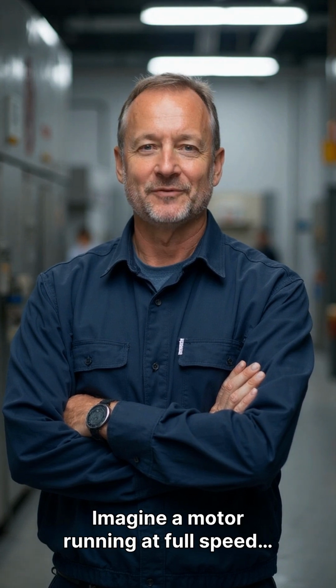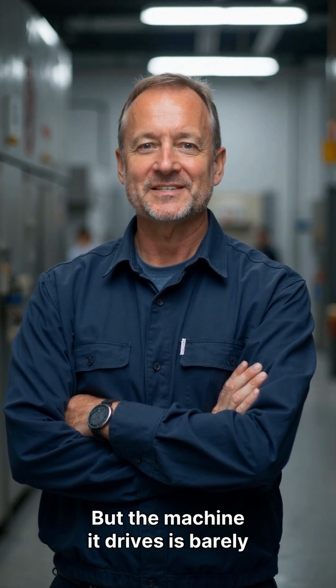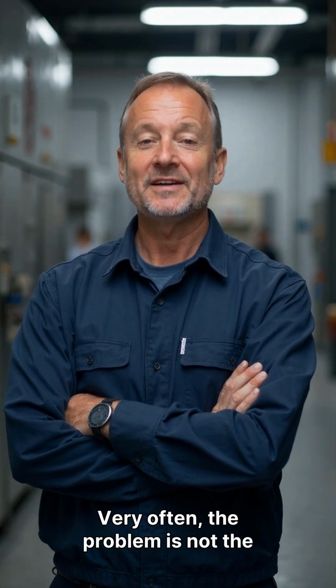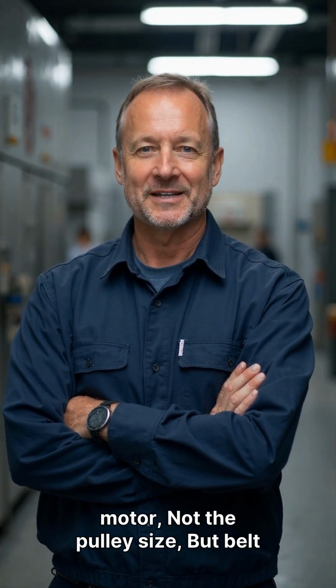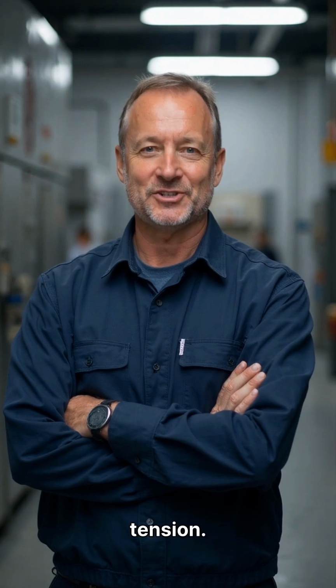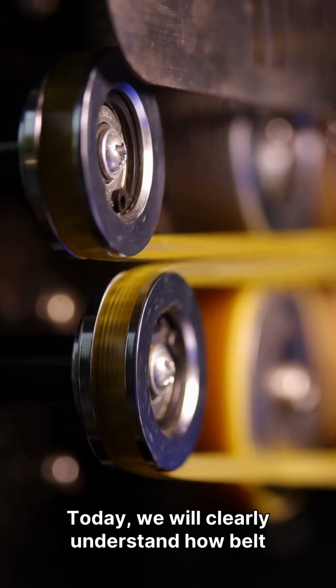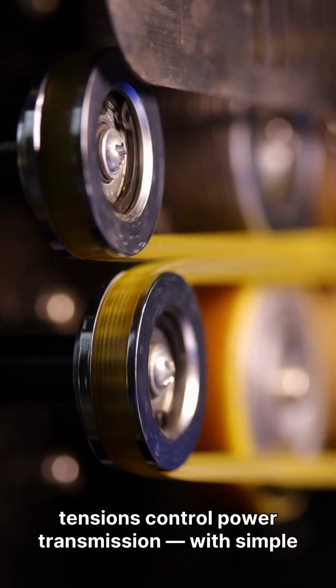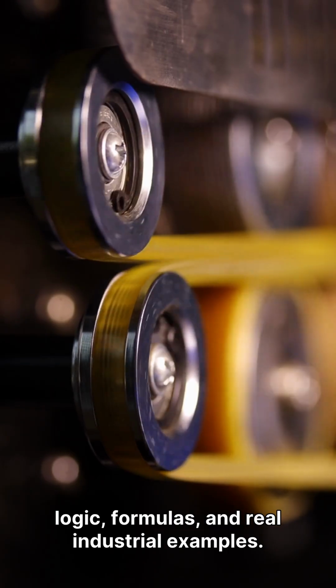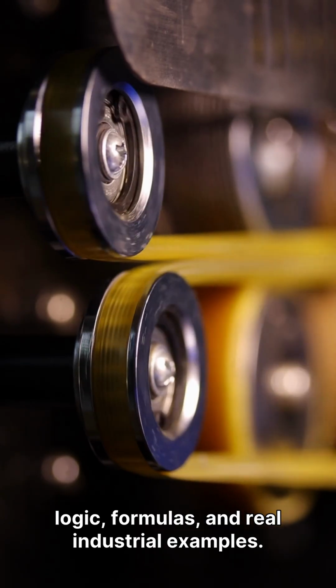Imagine a motor running at full speed, but the machine it drives is barely moving. Why? Very often, the problem is not the motor, not the pulley size, but belt tension. Today, we will clearly understand how belt tensions control power transmission, with simple logic, formulas, and real industrial examples.